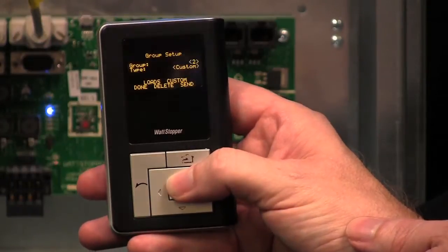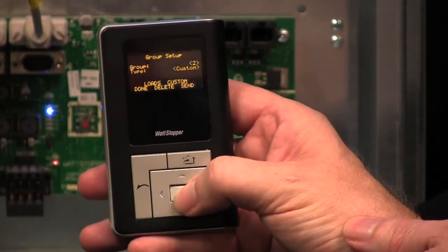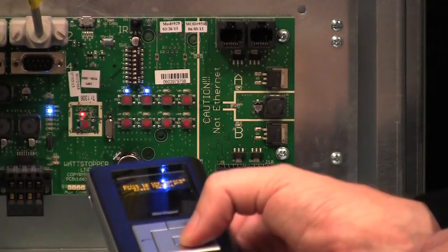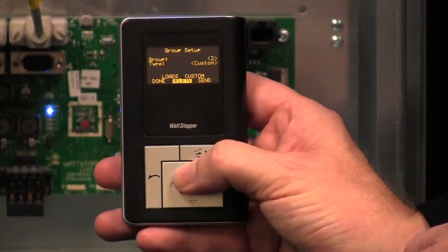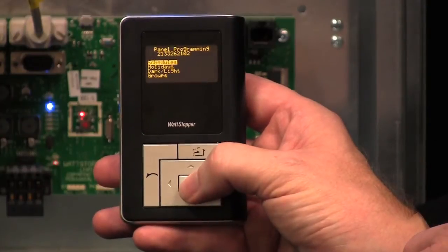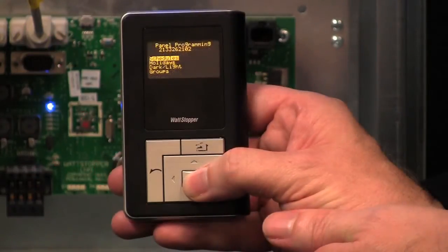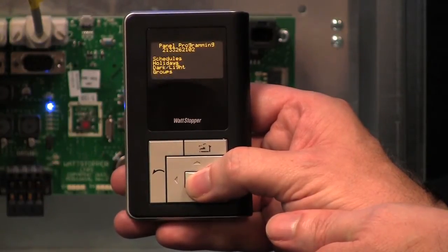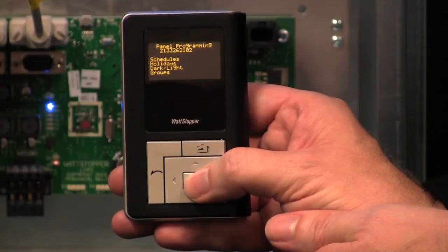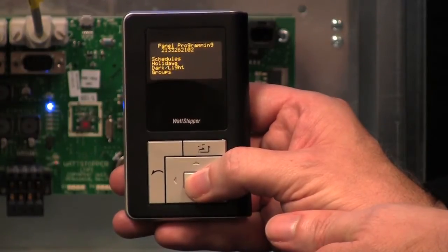I'm going to get all the way back to the top. I'm going to make sure I send this information into the panel. And then since I'm done here, I can now go back to the main panel schedule. So if you recall, the first group that we set up, group number 1, we just used a simple on and off command. You should use that whenever you have something that doesn't have occupancy sensors connected or typically have an after hours time delay.